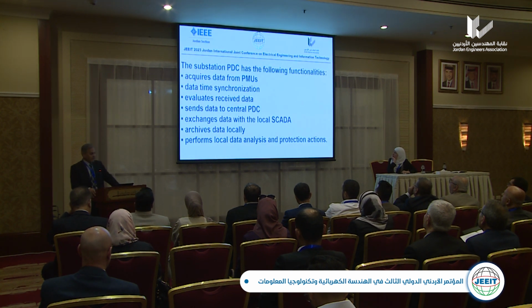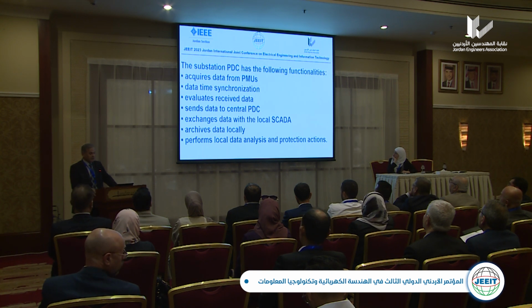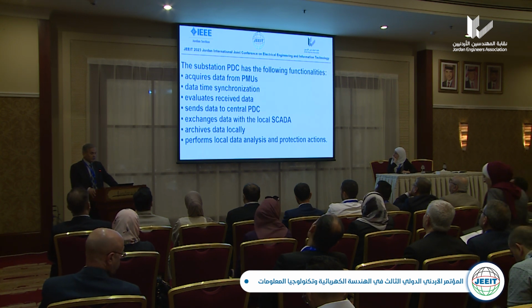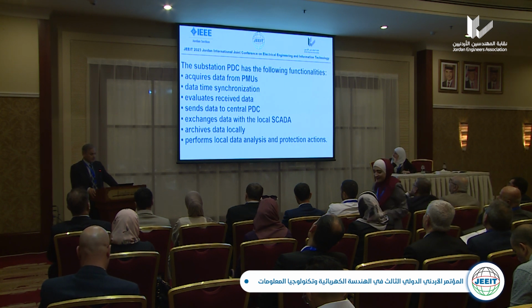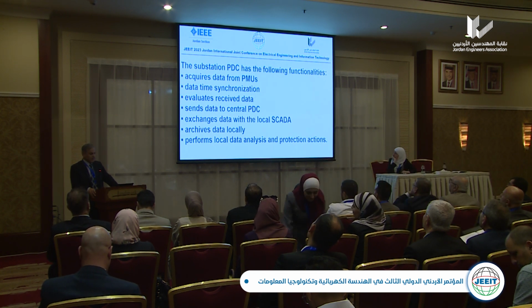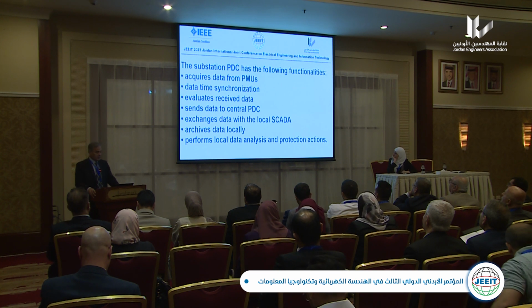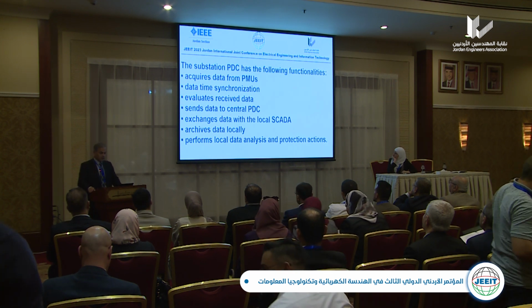PDC has the following functionalities: acquire data from PMUs, data time synchronization, evaluate received data, send data to central PDC, exchange data with the local SCADA, archive data, perform local data analysis and protection action.